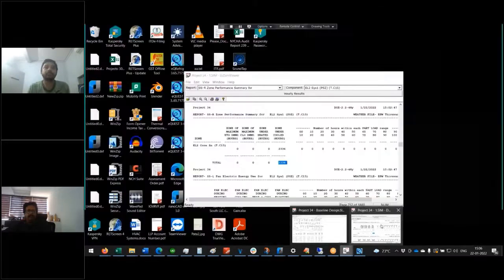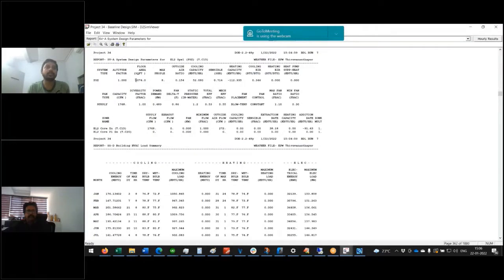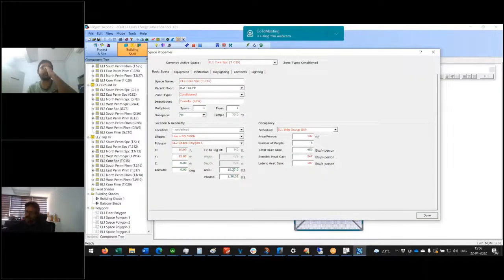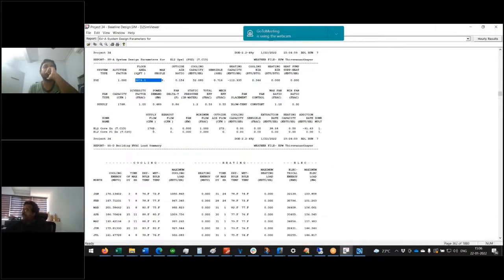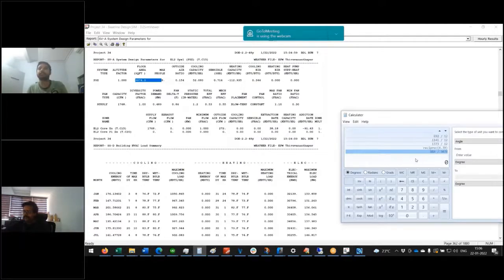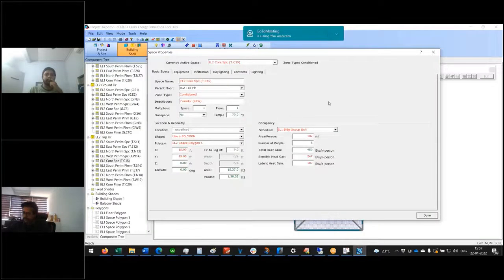So the area that you see here, this is for the entire, that includes conditioned and unconditioned zones. All right. So our actual area was 1537 just for the space. And now 1537, if I'm correct. So 1768 divided by 1537, in fact. So it's coming to about 1.15 CFM per square feet. So that's a start. I can probably take it up to 1.5 or maybe 2. 2 will be like maxed out. Ideally, it should not be greater than 2.